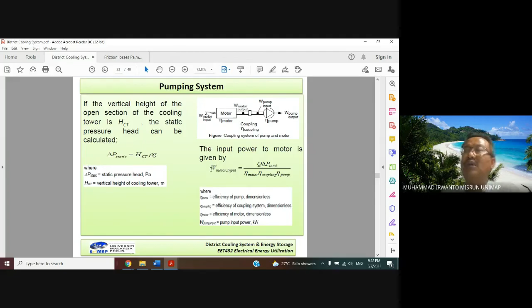And then, because the water flow rate Q is also obtained, we can calculate the input power of the motor. The input power of the motor is given by Q multiplied by delta P total over efficiency motor, efficiency coupling, efficiency pump. For Q, please use the unit in cubic meter per second, 0.139. Multiply by delta P total from here in Pa, 226,850, over the efficiency of motor, coupling and pump, given in the question.